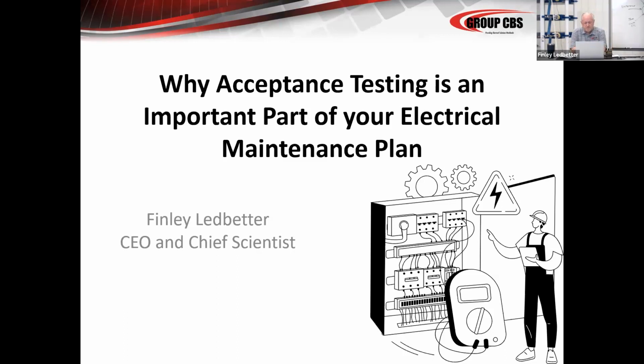It'll continue to change, but there is nothing on the drawing board today that satisfactorily will replace the air breaker in low voltage and the vacuum breaker in medium voltage applications. So what is reliability in switchgear? You cannot test it in. You have to bring it to the equipment through inspections, through proper lubrication plans, through all the things to keep it reliable, but it starts minute one with a credible, proper acceptance test to make sure that at least on day one, you have properly operating equipment.